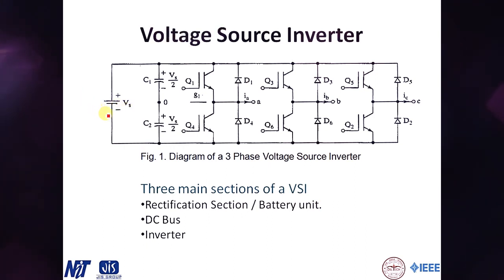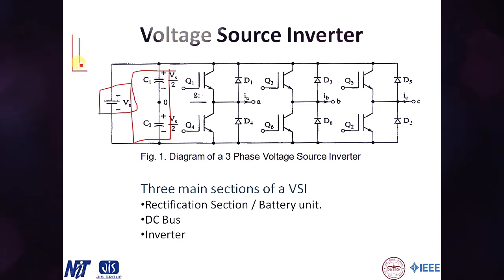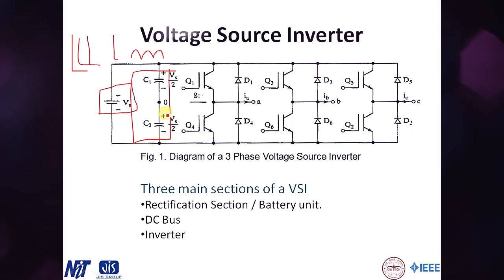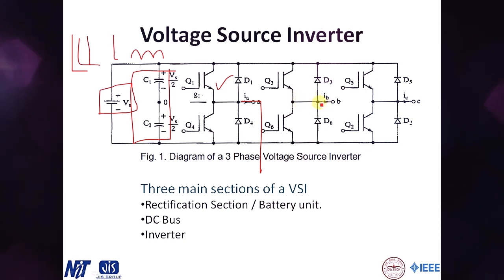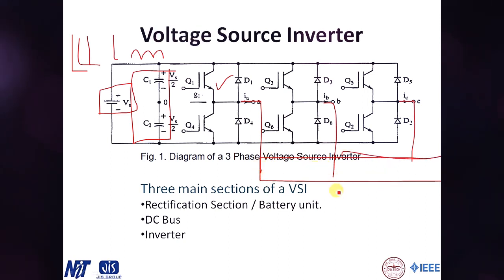This is what a voltage source inverter looks like. There are three sections: the DC battery or rectification section, a filtering section, and the switching section. After rectification we get a pulsating DC, so a filter capacitor converts it to linear DC. Finally, six IGBTs switch at different instants of time to produce a three-phase AC output on lines one, two, and three, which is used for driving motors or other purposes.